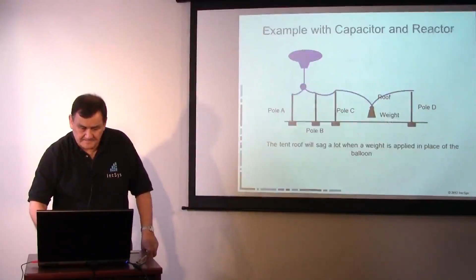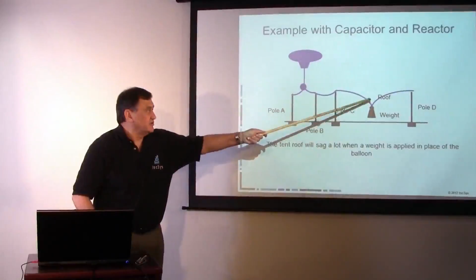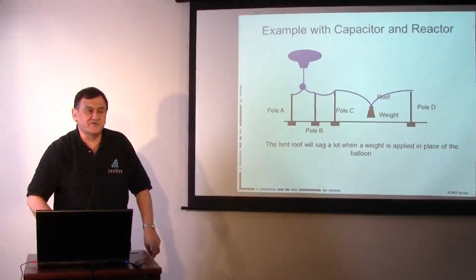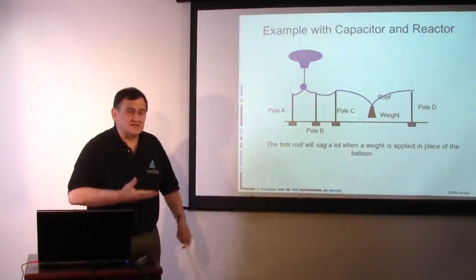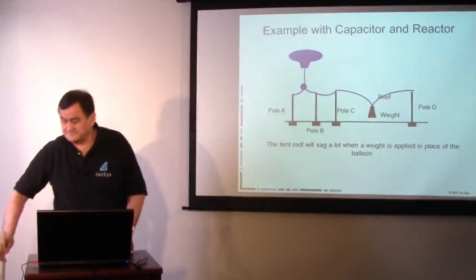So here's an example with the reactor. The reactor has the effect of dragging the voltage down. The amount that reactor will drag the voltage down depends upon how strong that bus is, which is a function of how close that bus is to your nearest generator, which has voltage regulating capability. When that generator hits its megavar limit, it's like the pole, like the lifter, it's sagging. So that generator has to be within its megavar limit to be able to hold that voltage at the particular set point.